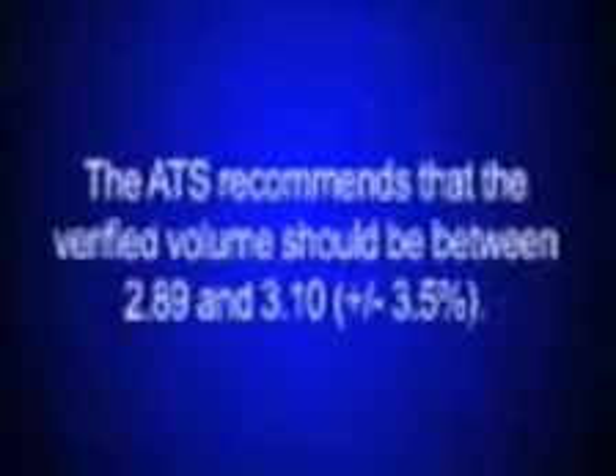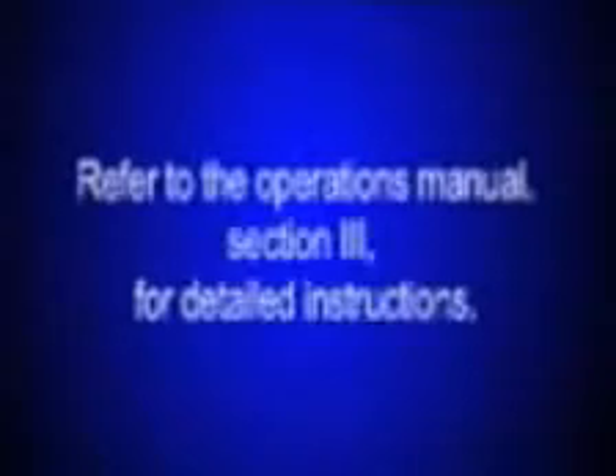Pull the plunger all the way out and inject the air from the syringe into the spirometer. It is important to maintain a smooth, steady motion when performing the calibration. Use the red dotted line and/or the blue timer arrow as a target flow rate. After 3 correctly performed calibration checks, the system will automatically calculate a correction factor and prompt you to perform 1 verification pump. The spirometer will display a pass or fail message once the calibration procedure has been completed. The ATS recommends that the verified volume should be between 2.89 and 3.10, plus or minus 3.5%, to be accepted. Refer to the Operations Manual, Section 3, for further detailed instructions.